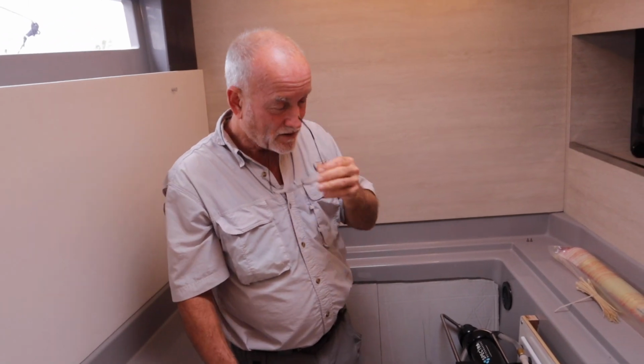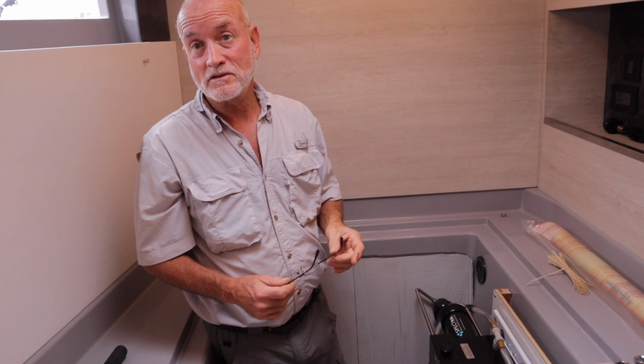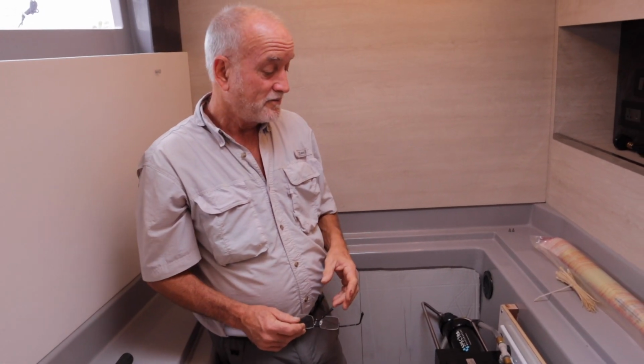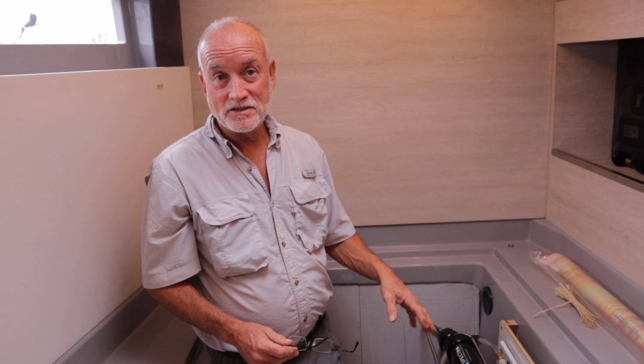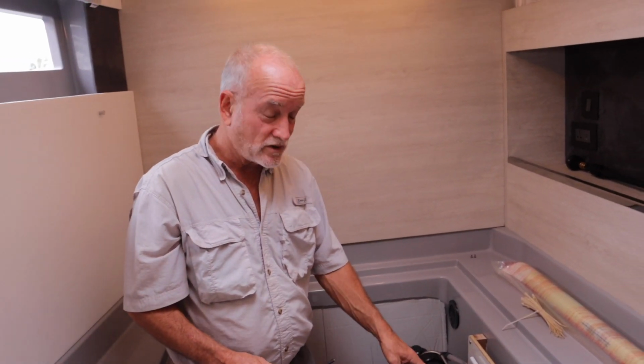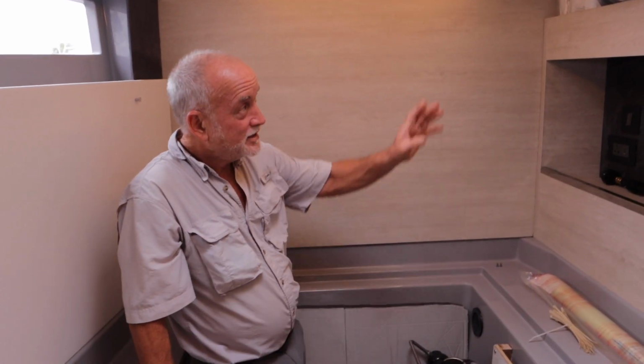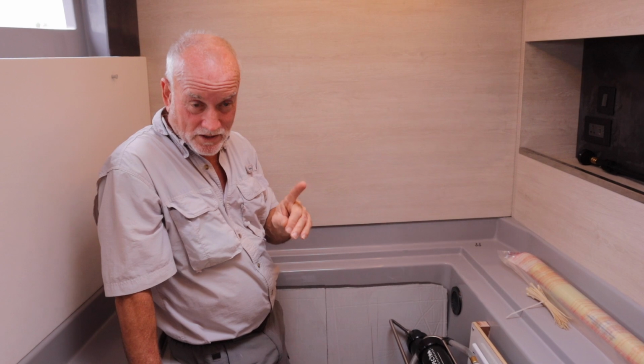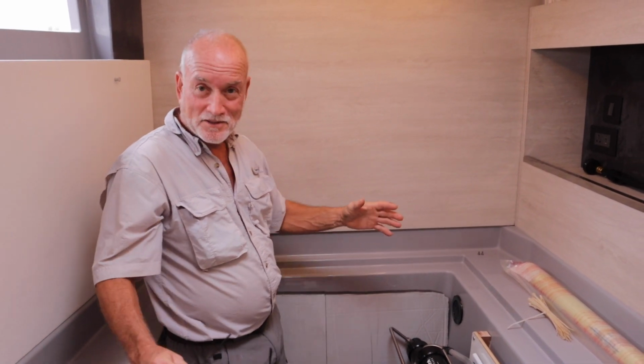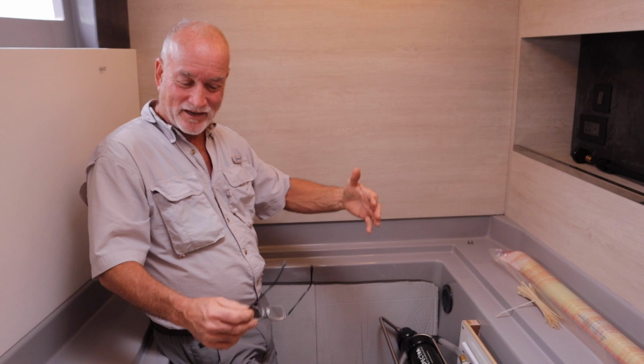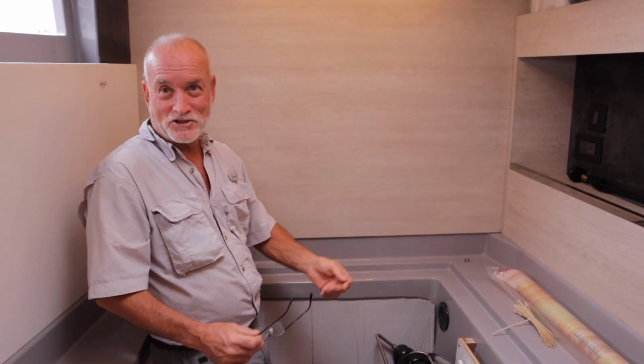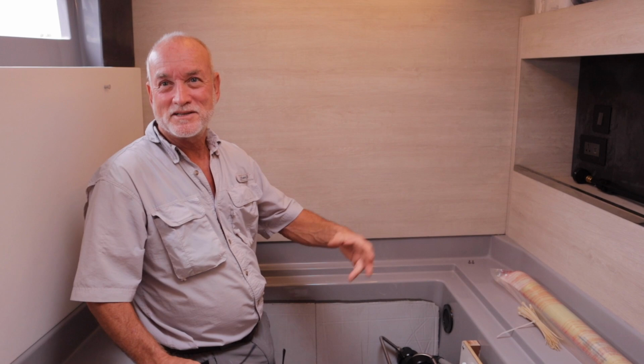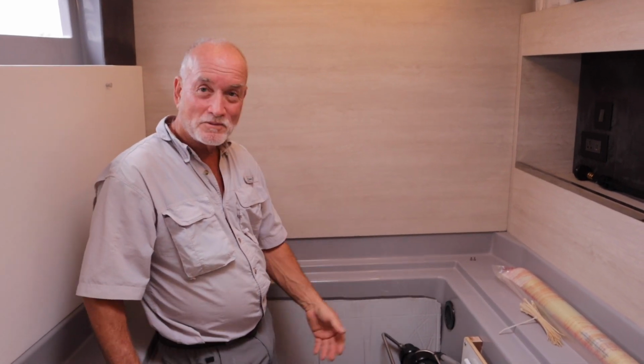Every other Watermaker company uses what's called sodium metabisulfite to pickle their membrane. If we put sodium metabisulfite in this system, it will pickle the membrane just fine, but it will destroy this pump and the warranty that comes with it. So don't do it. And this is like $25 a piece. It's a one-time use. Sodium metabisulfite. I'm a sailor, so I can say it. Sailors are cheap. They get a 5-gallon bucket like that for about $50, and they all chip in at the bar $3-4, and everybody's got a lifetime until they put it in a Spectra. Then it's $4,000 worth of repairs. So don't do it.